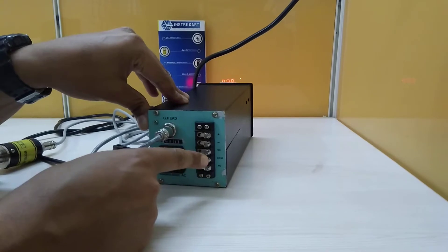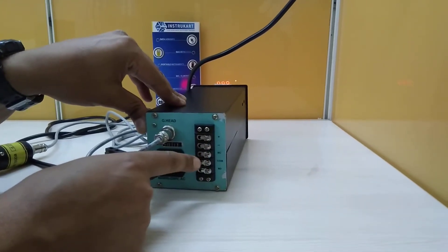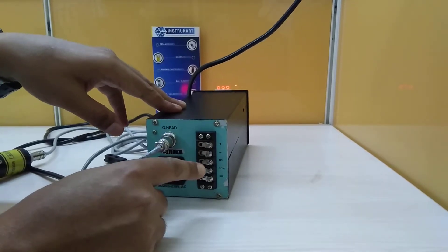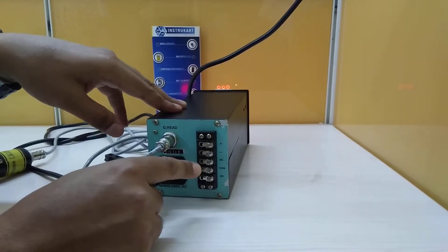This particular gauge at the back side we see that there is a setpoint control option where we have to, we can see that there is an NO and NC and communication with plus and minus.